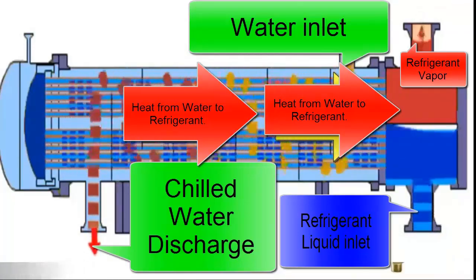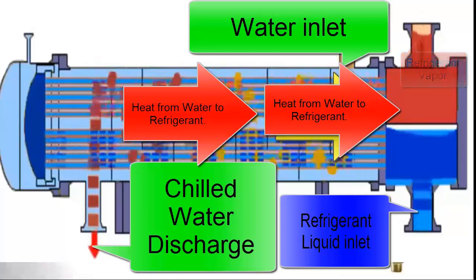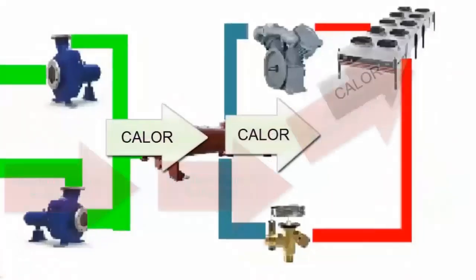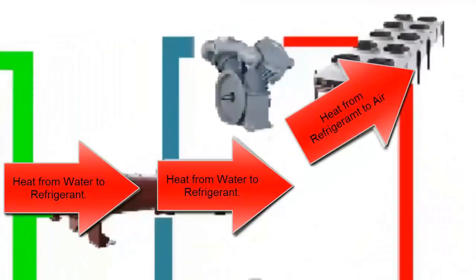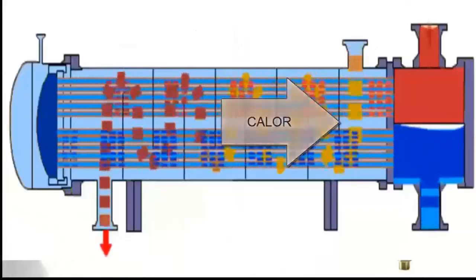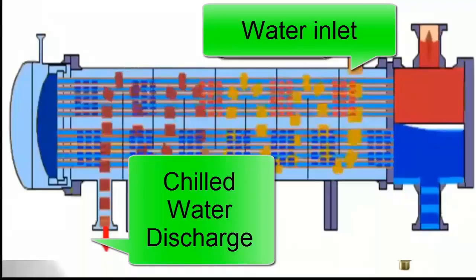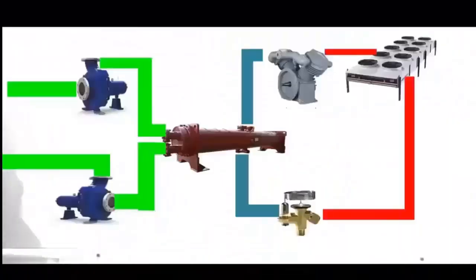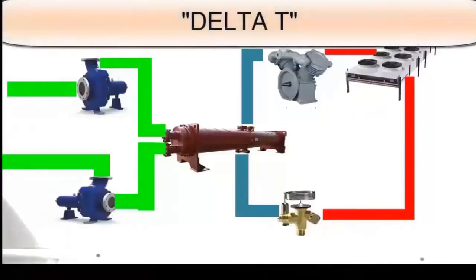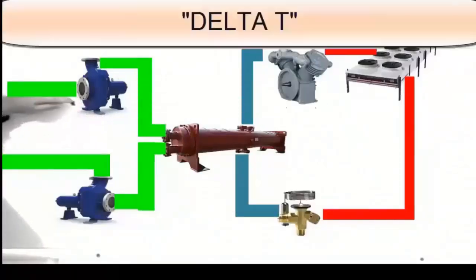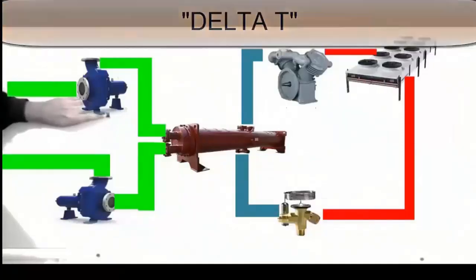The heat exchange in the cooler is a central process in the operation of the chiller. Water enters the cooler at a higher temperature, and thanks to the thermal exchange with the refrigerant, its temperature decreases significantly. This cooling process is what allows the chiller to fulfill its main function of maintaining a controlled temperature in the system. A key technical term in this process is delta T, which represents the difference between the inlet and outlet temperatures of the water in the cooler.